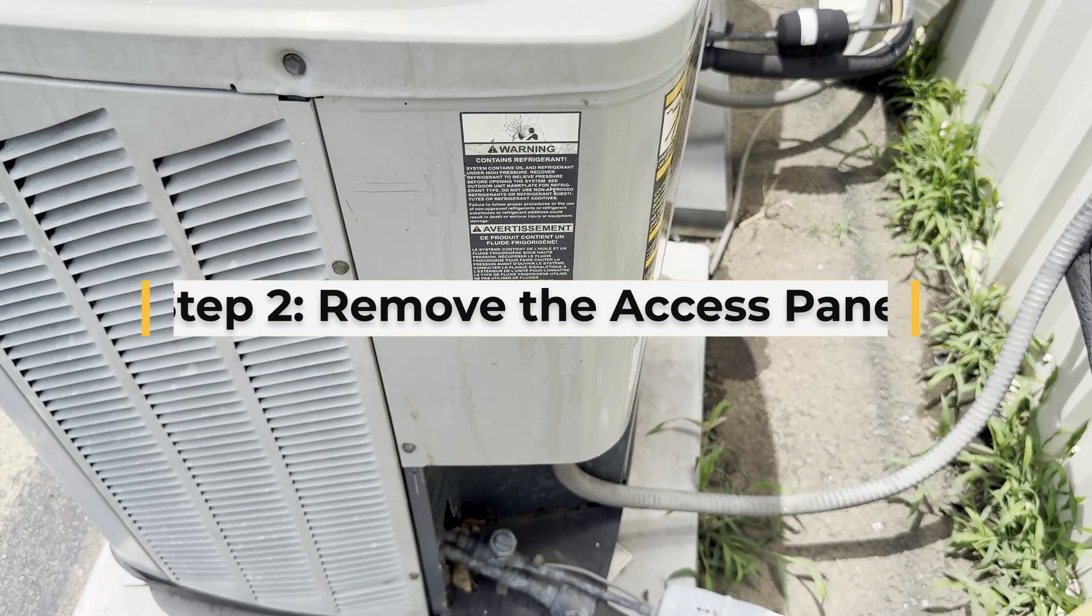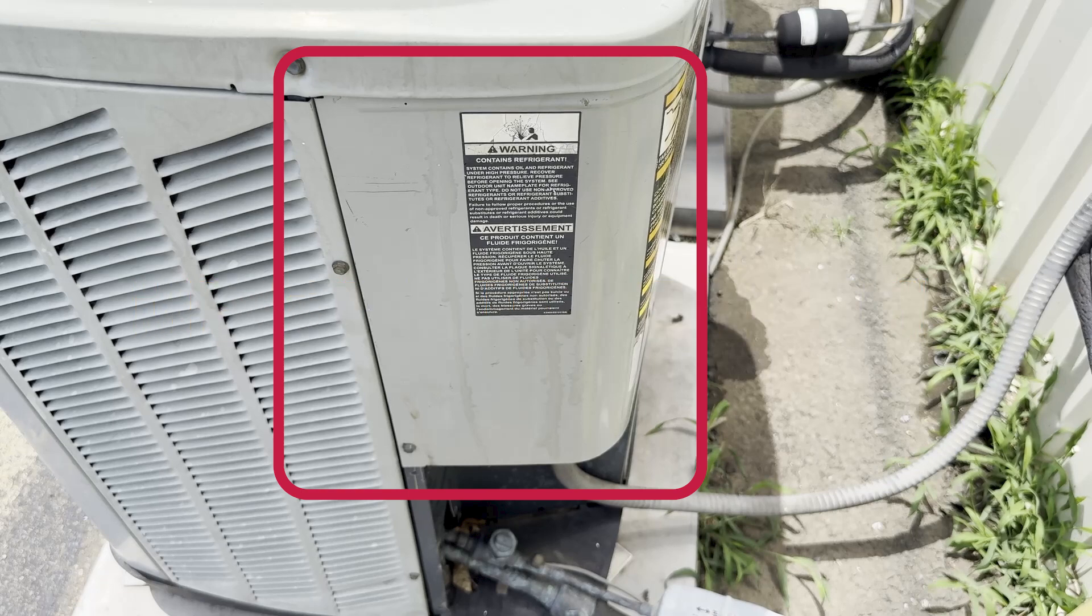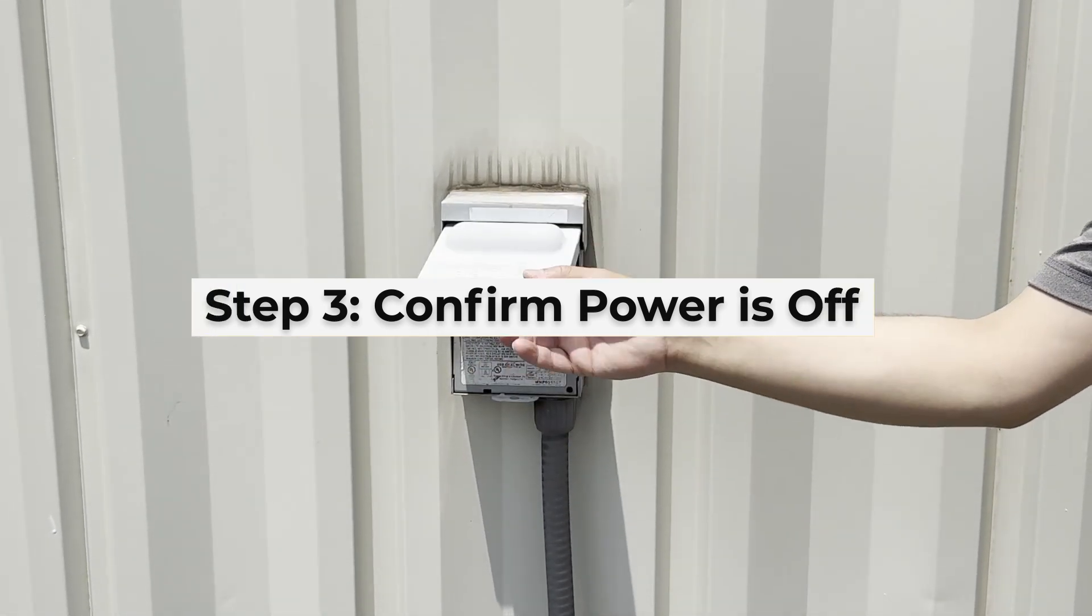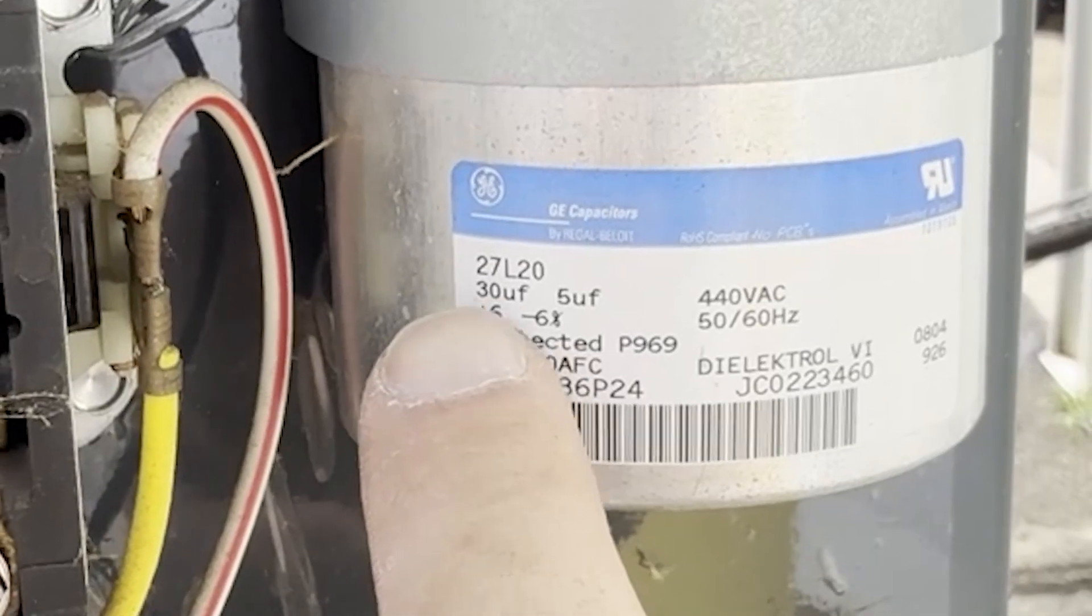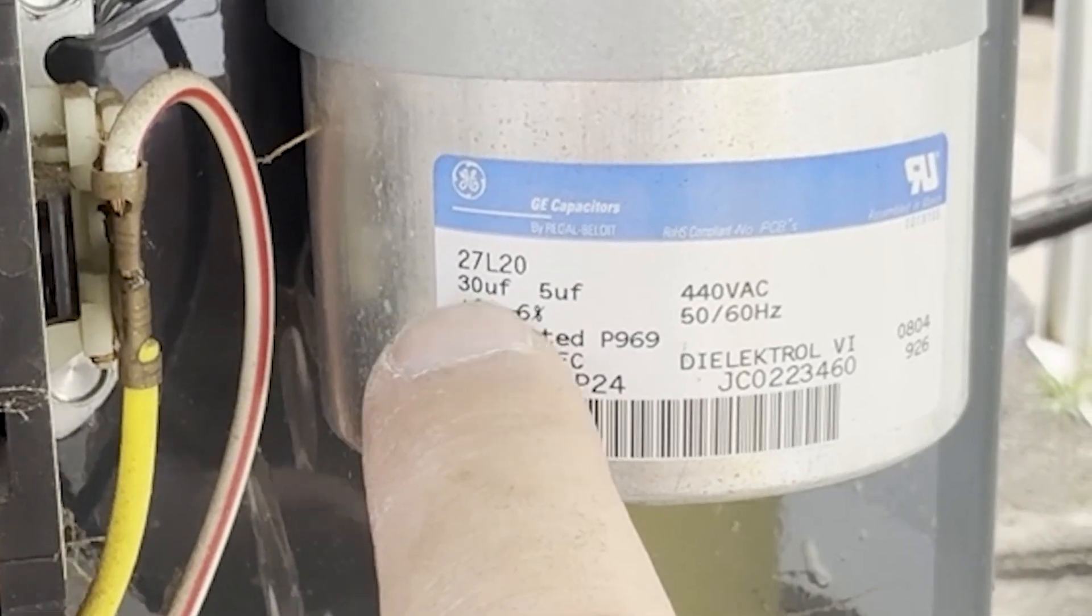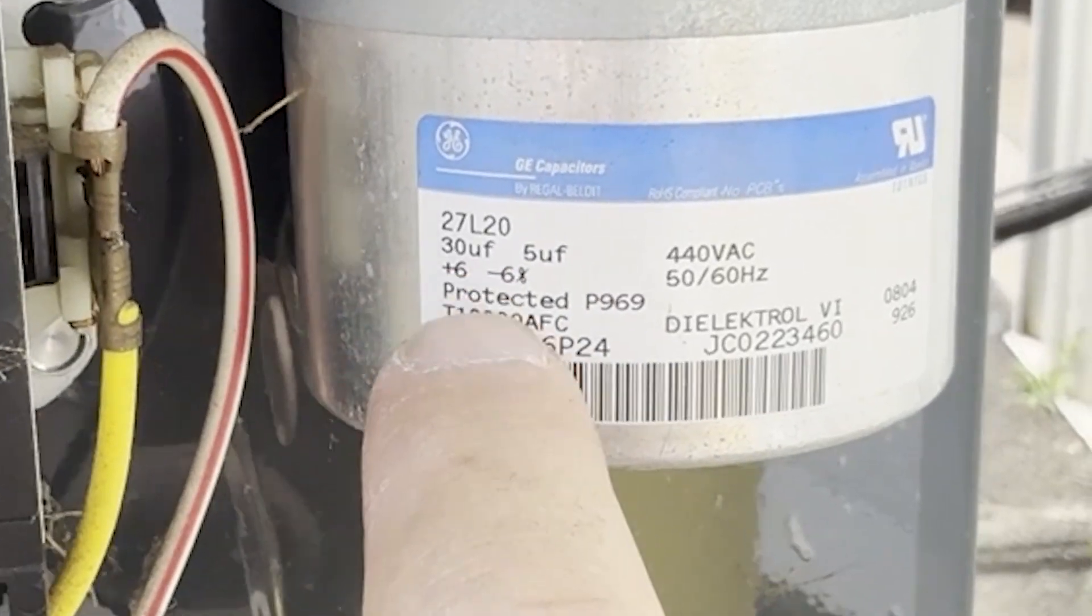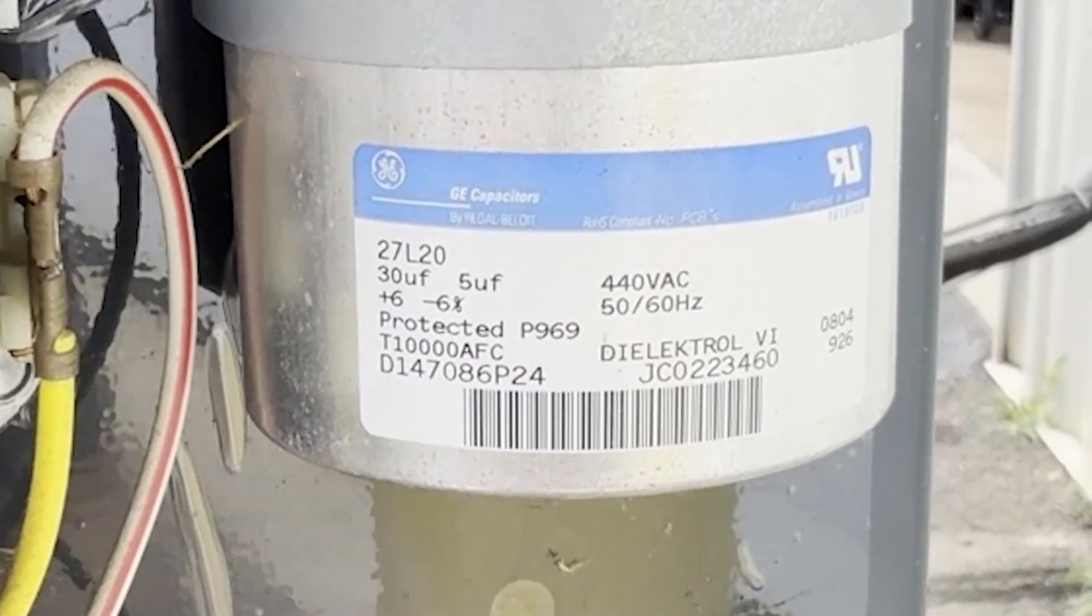Step 2: Remove the access panel. Use a 5-16ths nut driver or a regular screwdriver to remove the screws holding the side panel. Step 3: Confirm the power is off. Even though we pulled the disconnect, double check with the multimeter. Now, check the label on your capacitor. Ours reads 30x5 microfarads plus or minus 6%, 440 volts. We'll need this info later when replacing it.